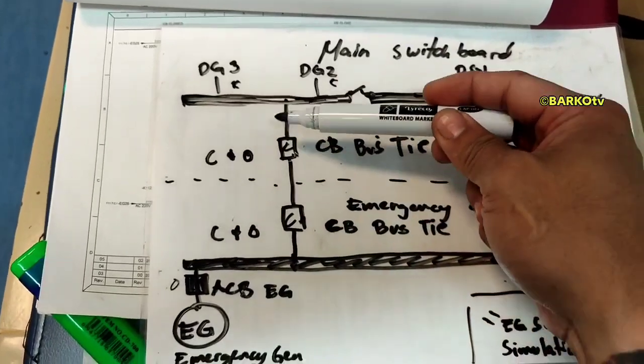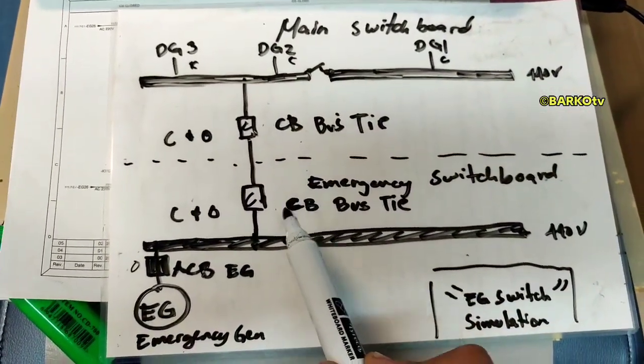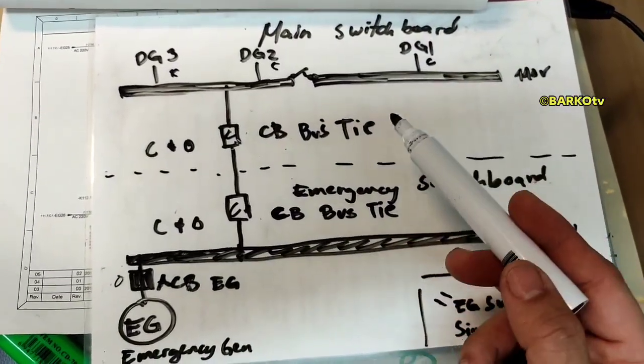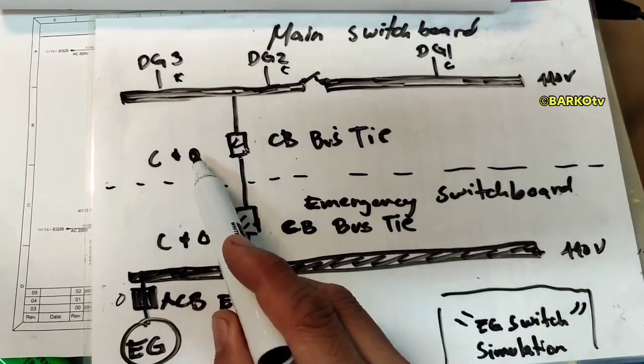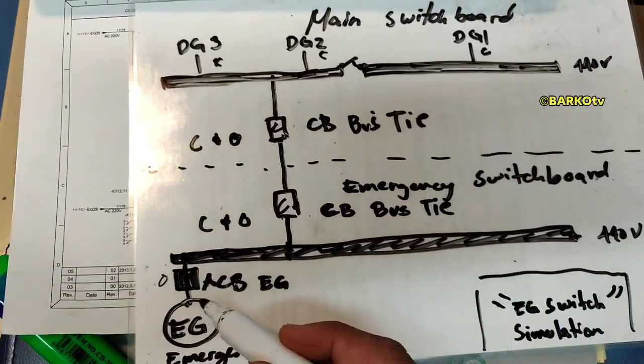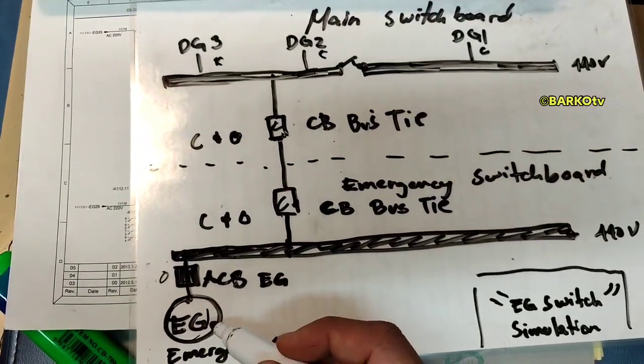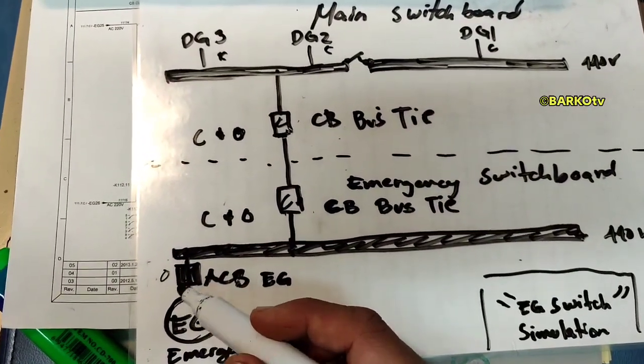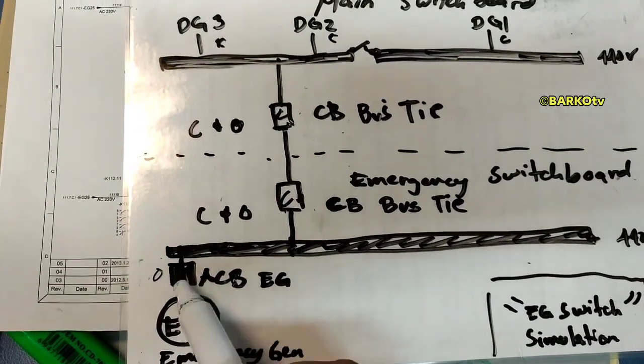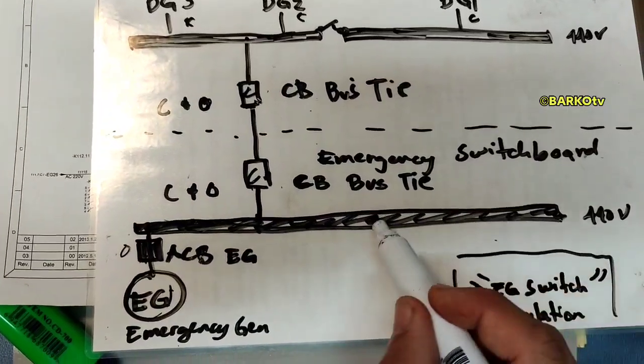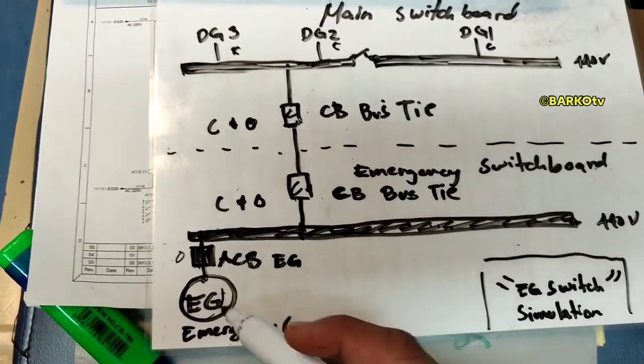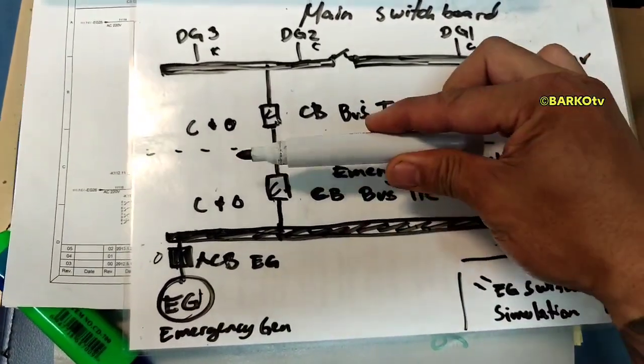During blackout test or simulation, if you open the bus tie located at the main switchboard, it will automatically run the emergency generator. Then there is a time delay, after which the ACB will close and supply the emergency switchboard — 440V — meaning there is power coming from the emergency generator.